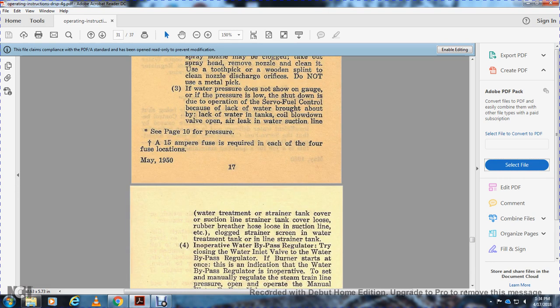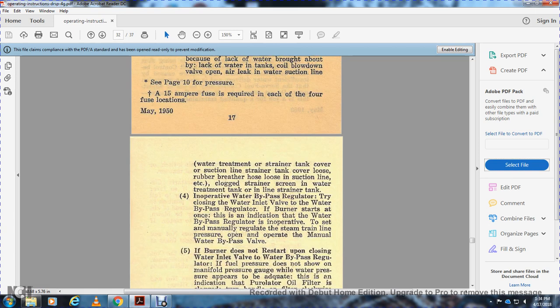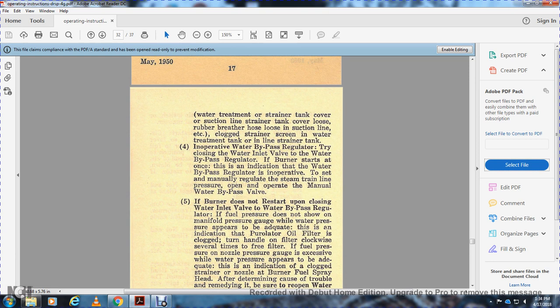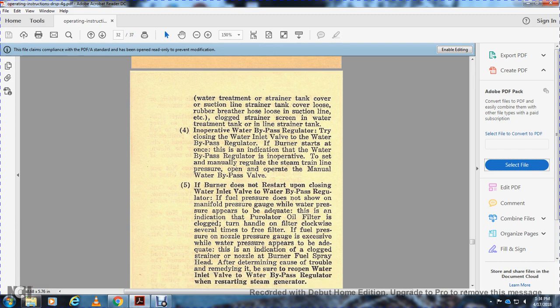Check the water treatment and strainer tank cover on the suction line. The strainer tank cover may be loose, or the rubber breather hose may be loose in the suction line. The strainer screen in the water treatment tank of the line strainer tank may be clogged. For an inoperative water bypass regulator, try closing the water inlet valve of the water bypass regulator, and the burner should start. Set the steam train line pressure manually by opening and operating the manual water bypass valve. If the burner does not restart, open the water inlet valve of the water bypass regulator.